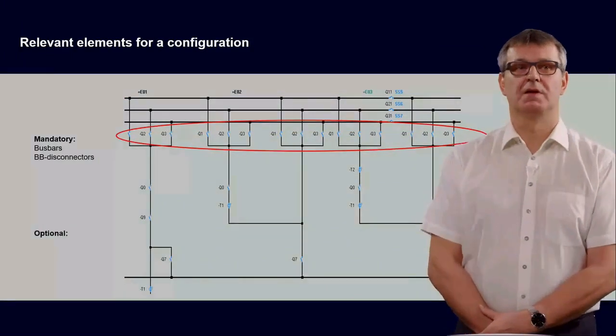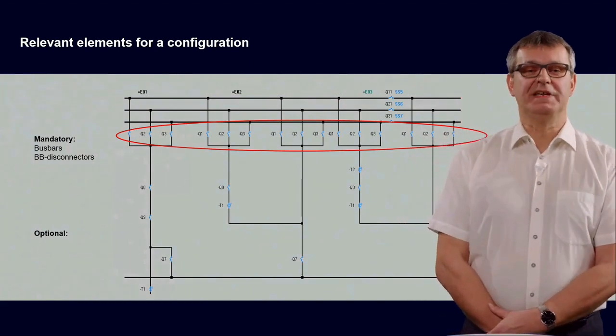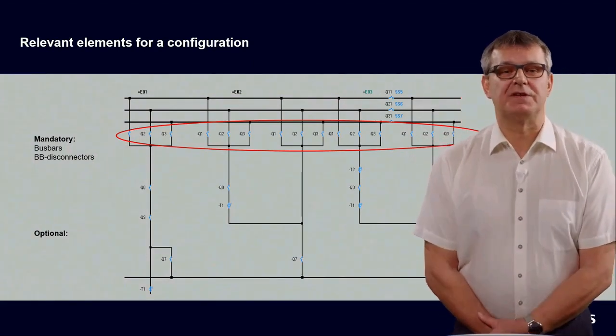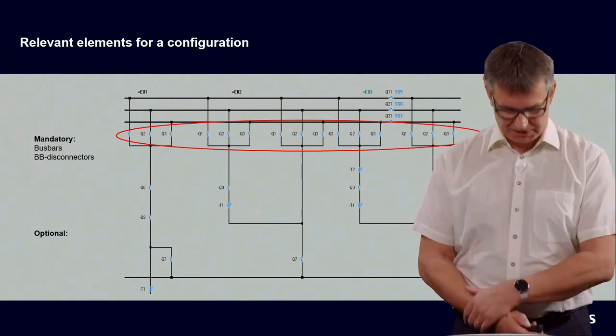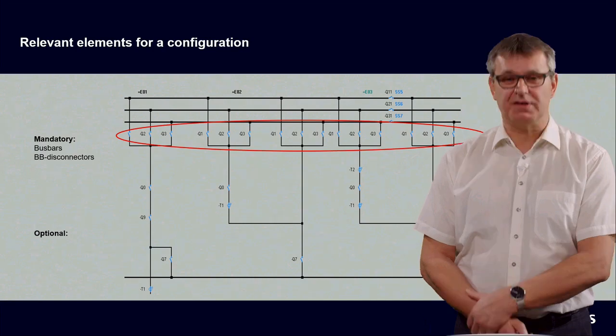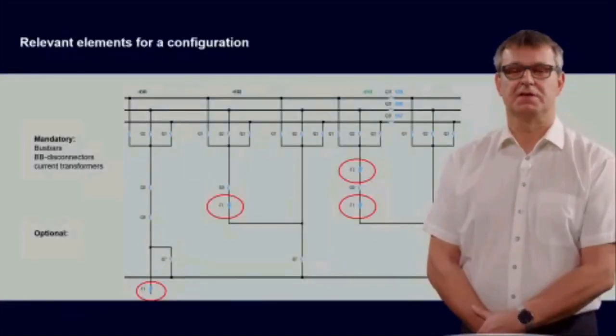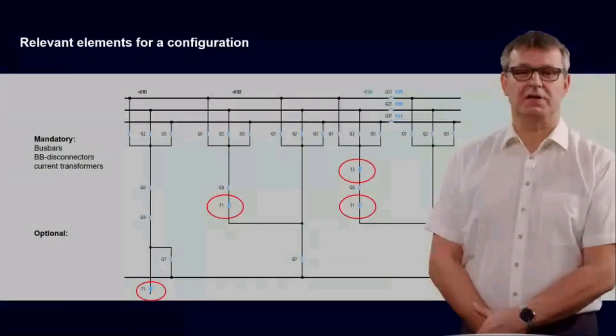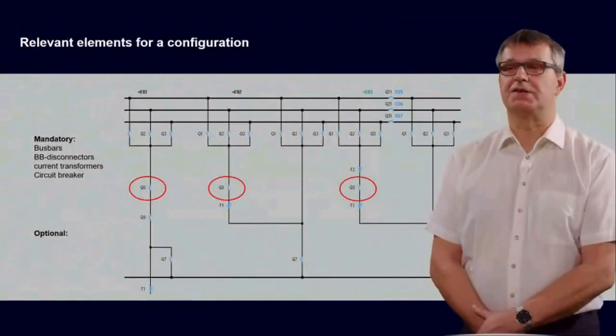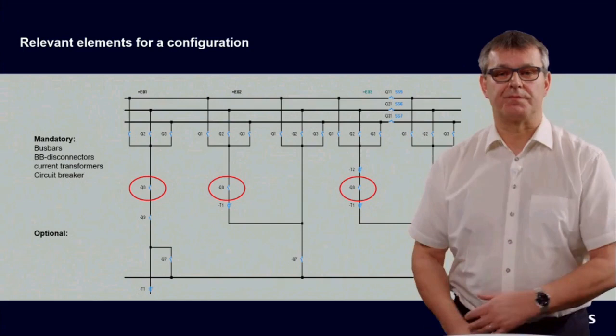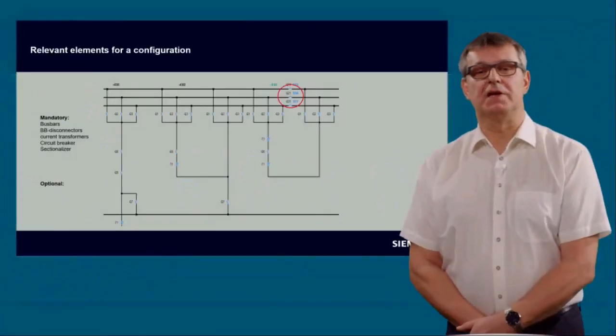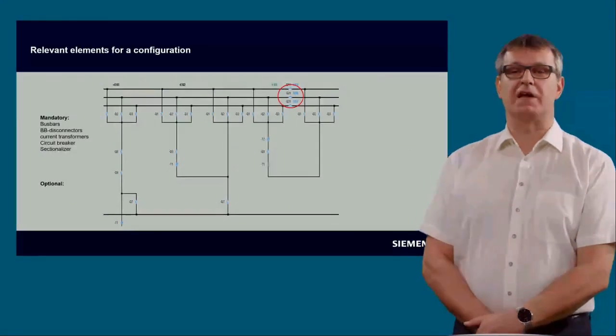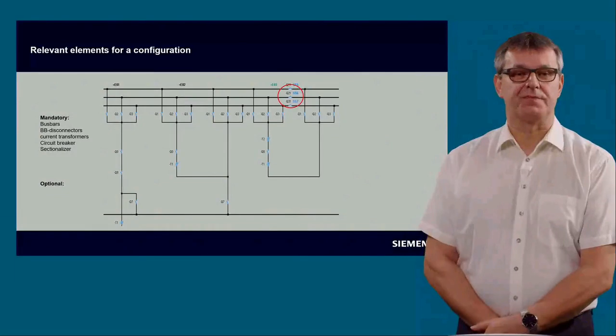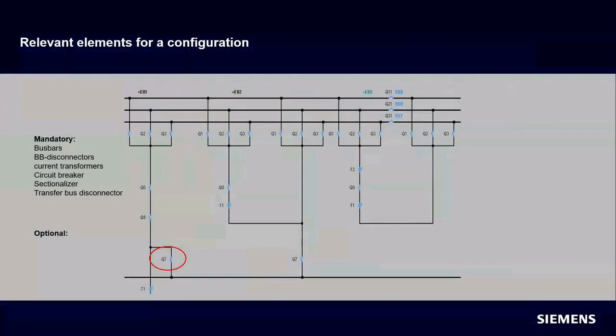We need the busbar disconnectors, which you can see here. We need to configure the current transformers, also seen with these red circles. And we need the circuit breakers. If available, we also have to configure the sectionalizing disconnectors, and if available, the transfer bus disconnectors. Optional only are the line disconnectors.